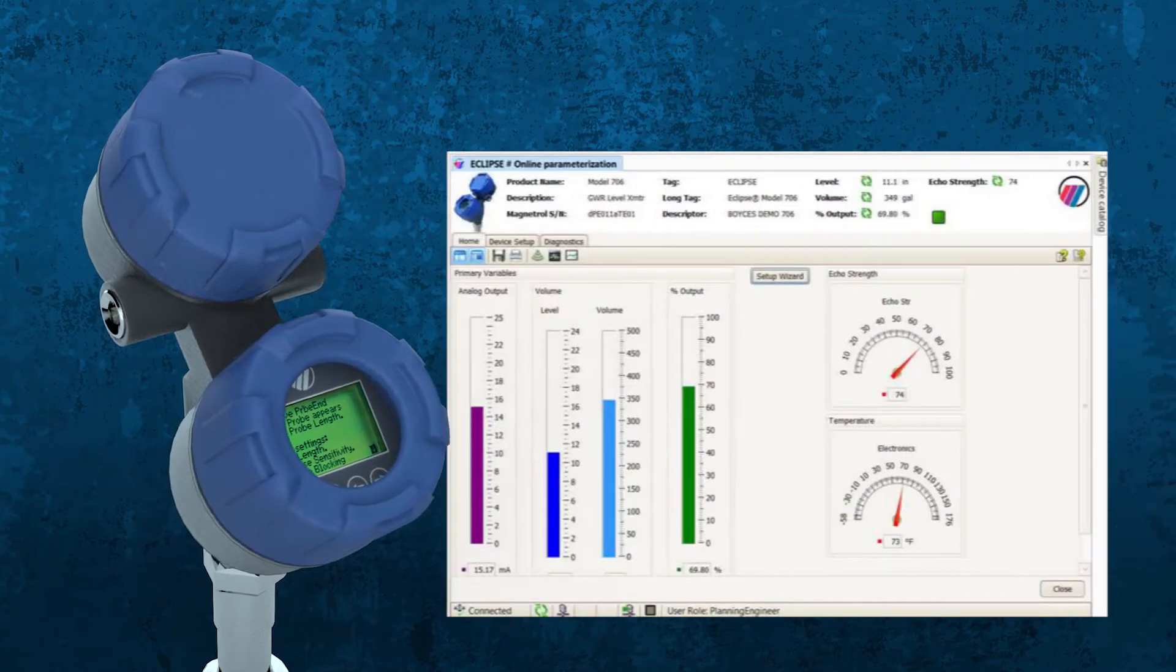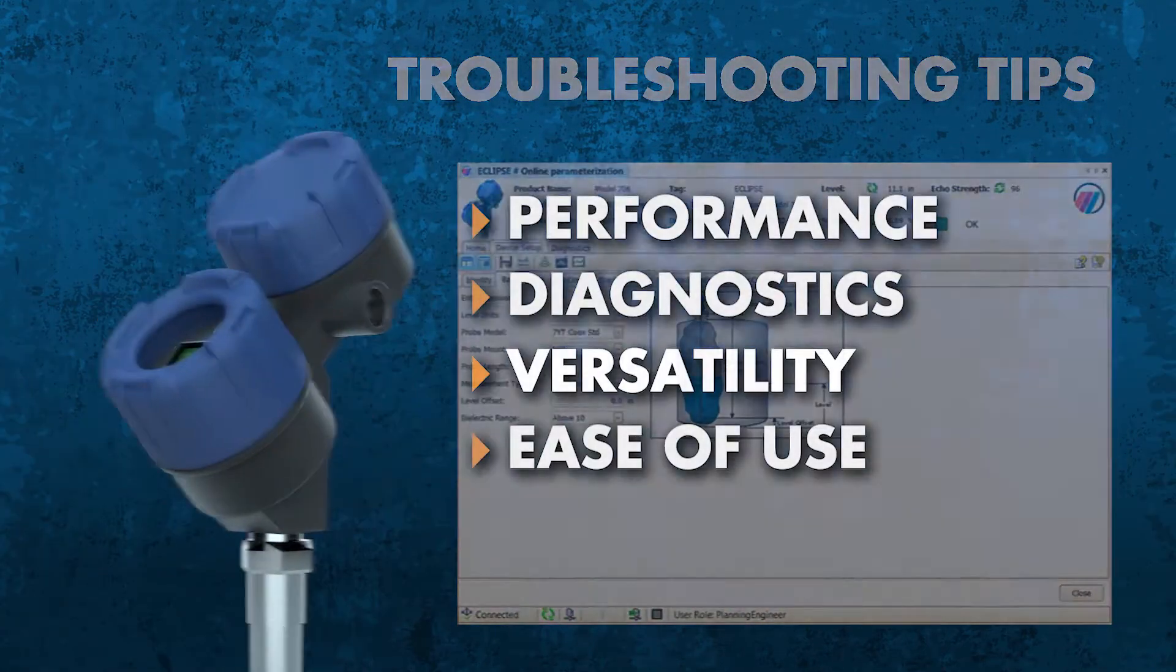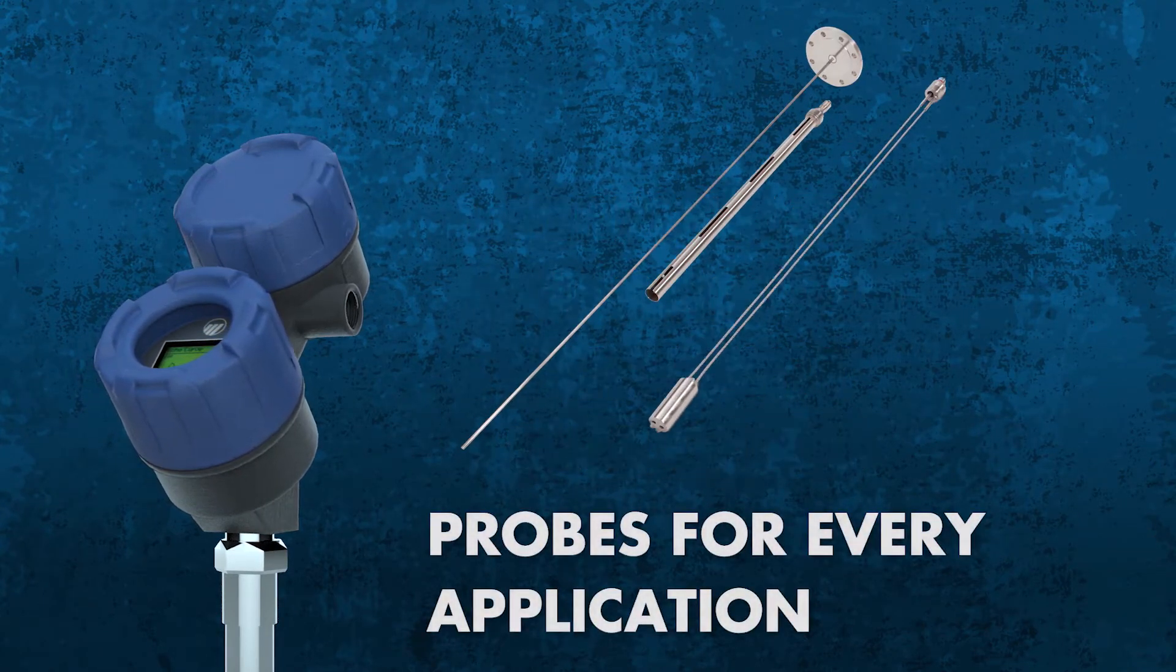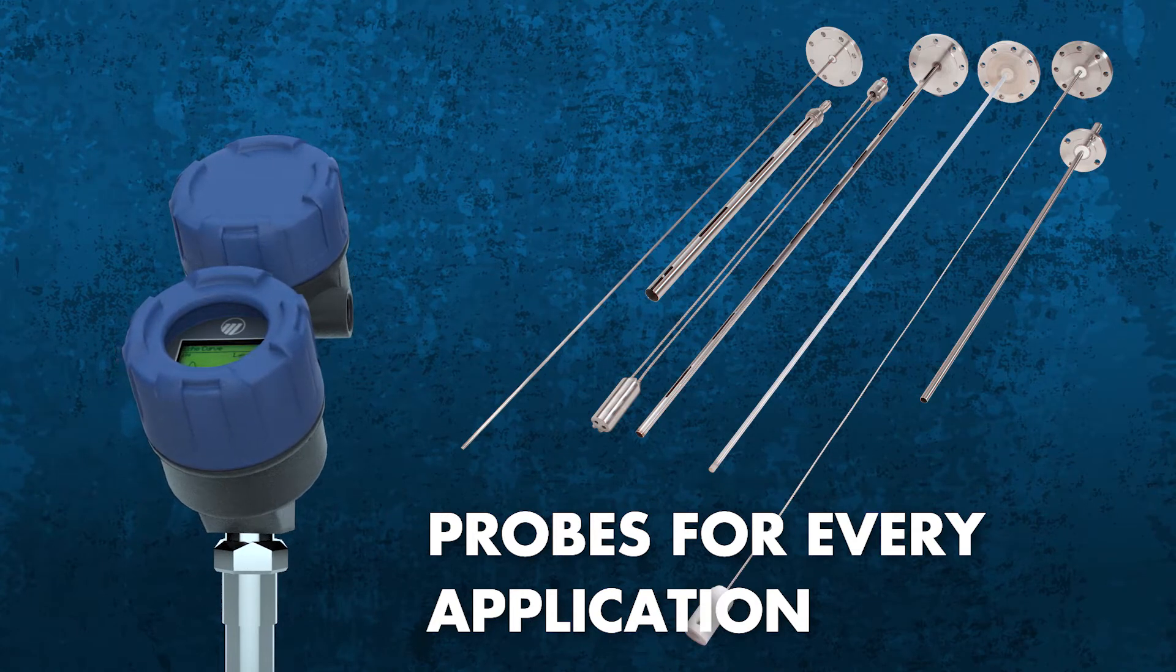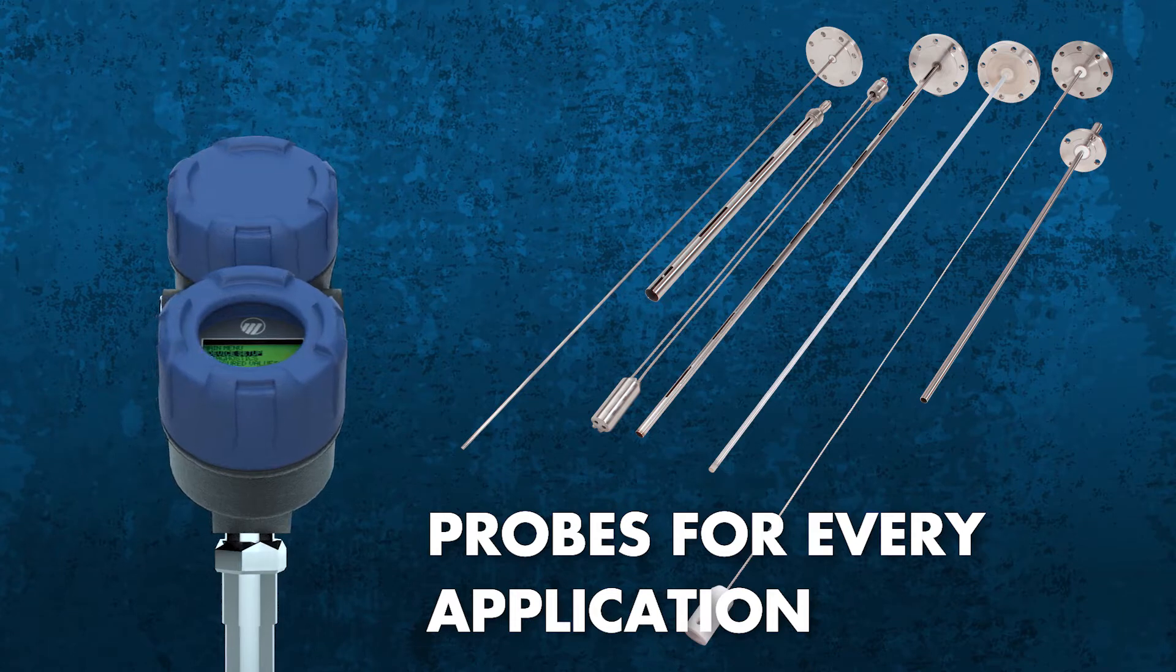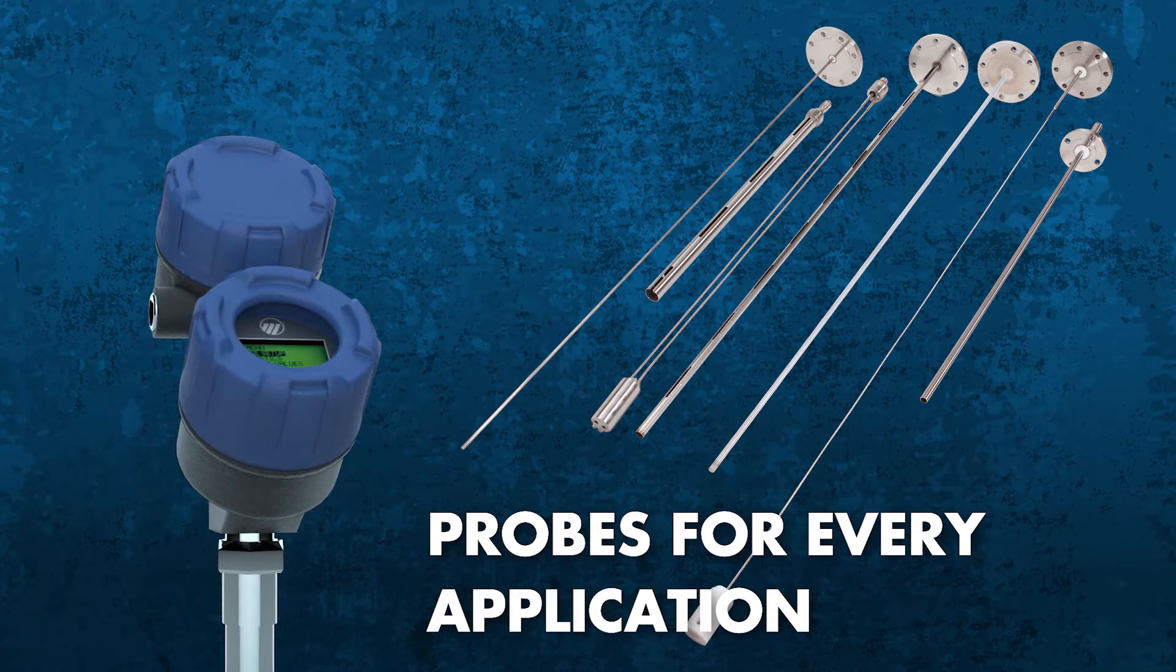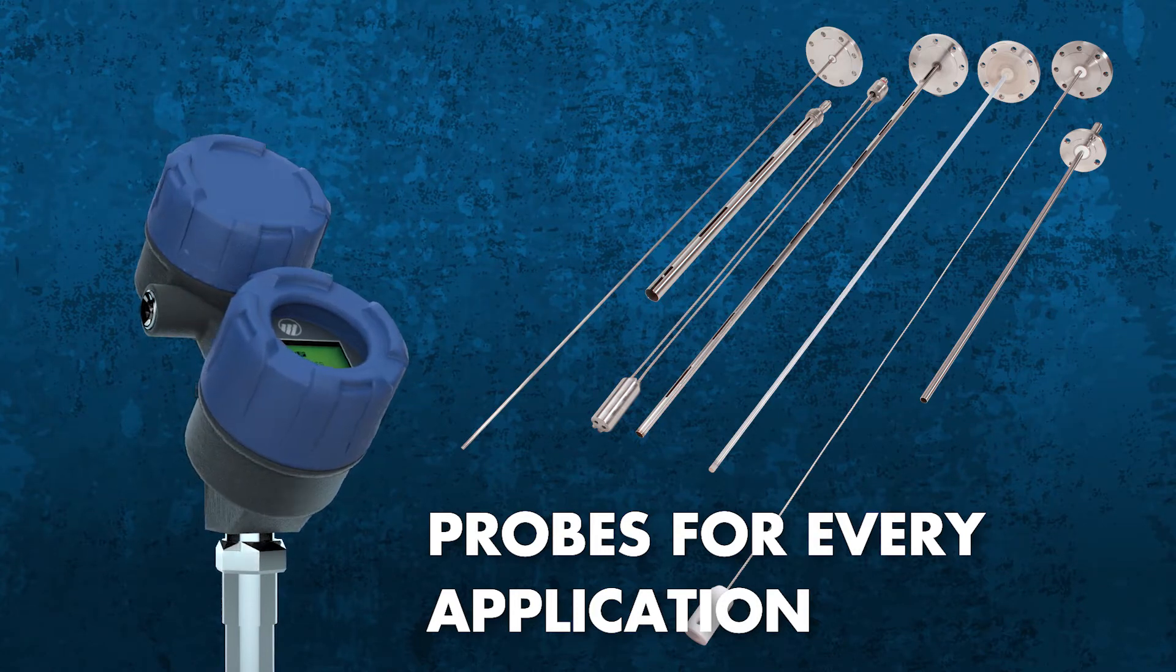The Model 706 also redefined versatility. It offers probe configurations for every application, so it can go from short to tall tanks, from dirty applications to hygienic installations, from cryogenic to 450 degrees Celsius or 850 degrees Fahrenheit, and from full vacuum to 431 bar or 6,250 psi.